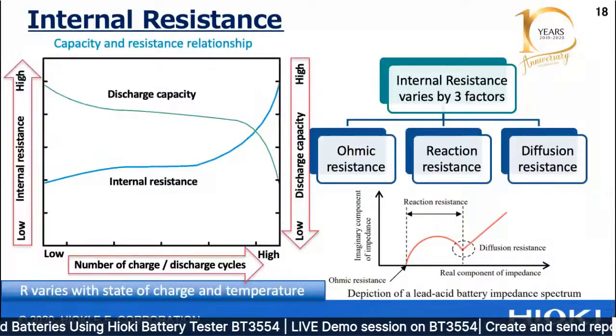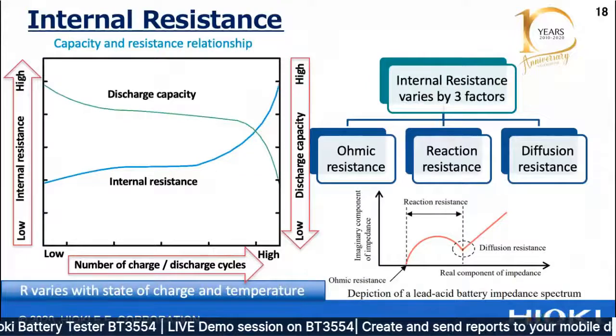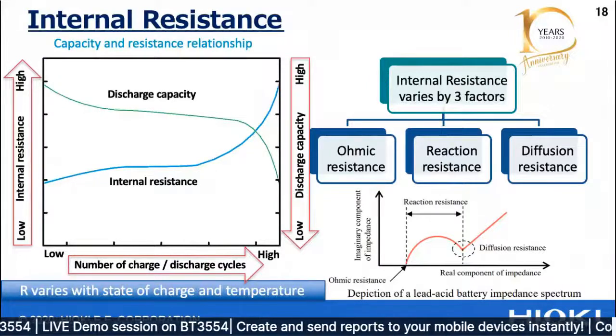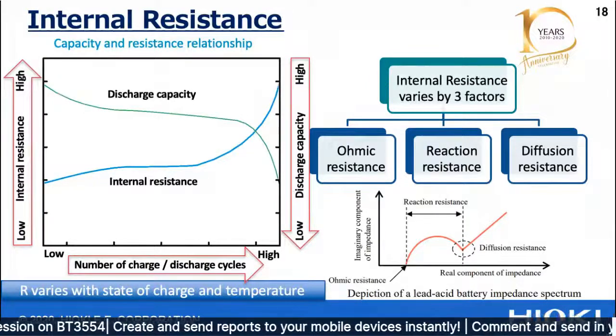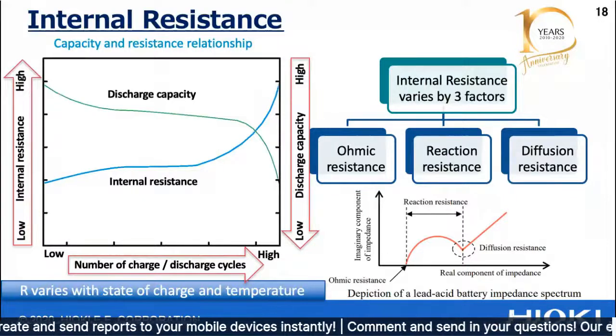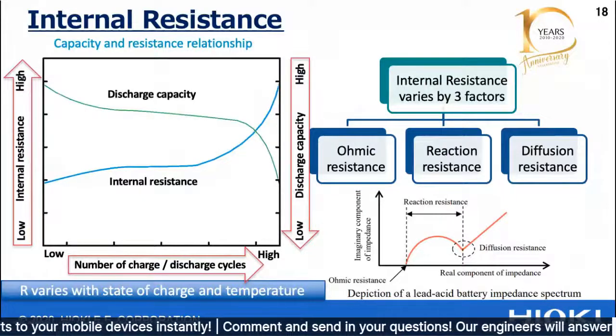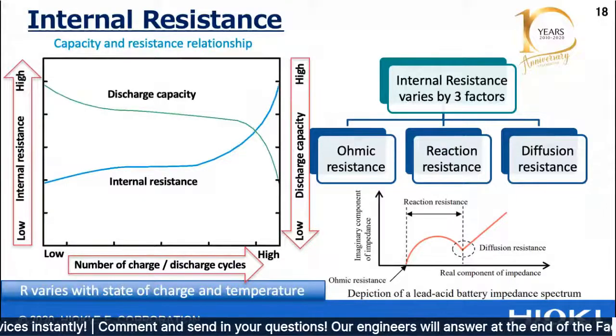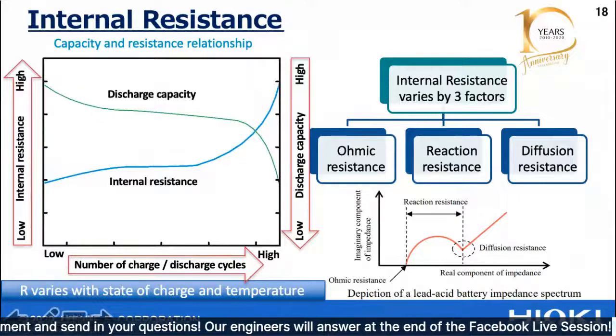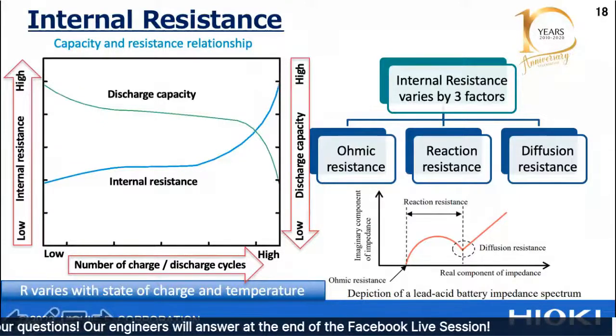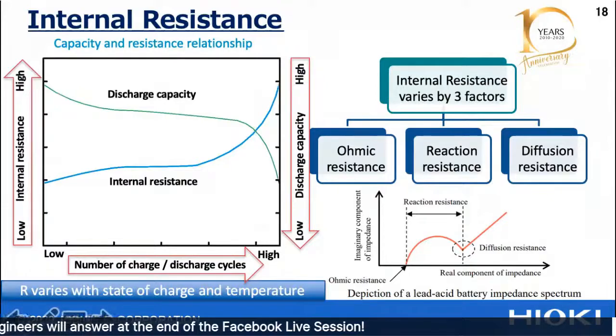Then we have ACIR testing to test the internal resistance of batteries to judge the health state with reference to manufacturer specs. Naturally, as the number of charge and discharge cycles increases, the battery's internal resistance will increase, which causes the discharge capacity to decrease.